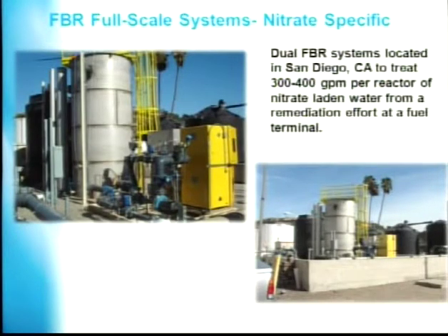I put this system up just as an example. This is a facility down in San Diego at a fuel terminal where they have nitrate. If you've ever been to Qualcomm Stadium where the Chargers play, underneath it is a massive fuel plume, and they're constantly doing remediation. After they remove the BTEX and the MTBE, they also have nitrate. Before discharging into something called Murphy Canyon Creek, they treat using 2 different FBRs in series. About 5 years ago they built one, and then 3 years ago, because they like the technology so much, they built a second unit, and they're able to fully treat that nitrate before discharge. And that doesn't have a filtration mechanism on the back end.